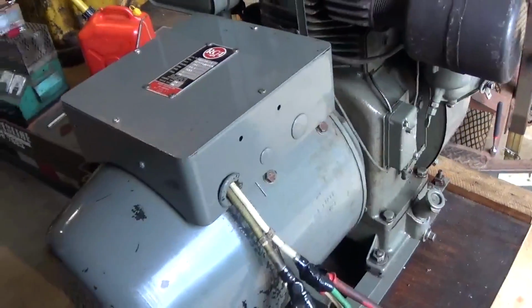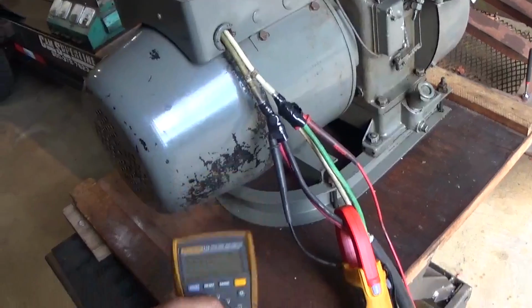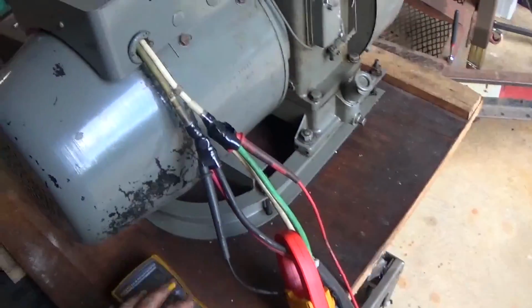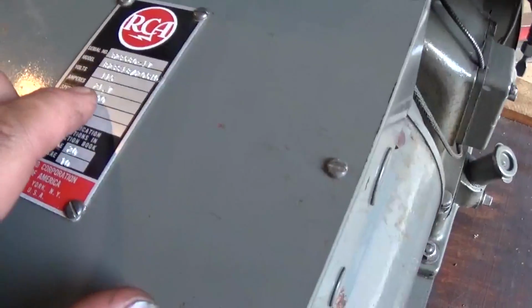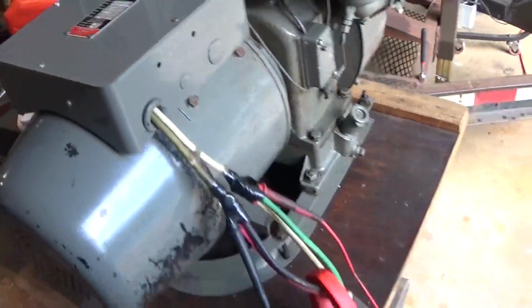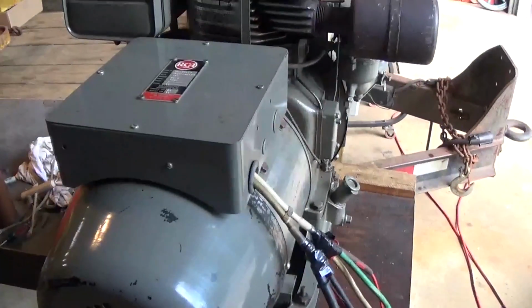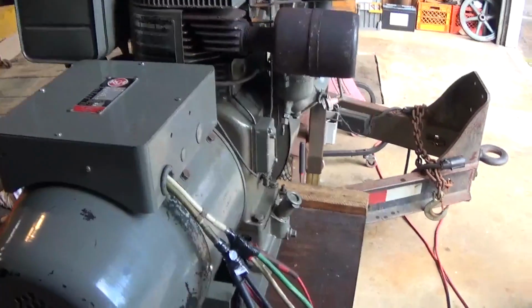Well, let's put some load on it. Let's get it to about 50% load and check the frequency again. Full load is 21.7 amps, so let's hit 10 or 11 amps and see where our frequency is.